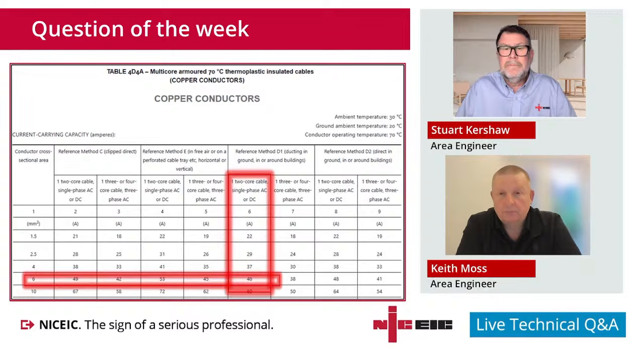So it's an addition in the Orange Book in Amendment 4, 2026. It's something that had always been around in the HDs, they always had two separate current carrying capacities based on the different installation method, but we only had a combined one. If you look down the columns there's not a huge difference, but it might make a sizing difference, certainly when you get to the larger cables, it might mean you don't have to go up in size.